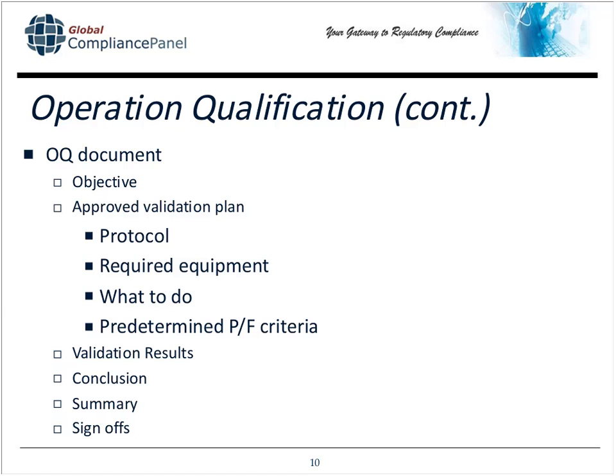Generally speaking, the OQ document is going to have an objective, what you're trying to do, and the approved validation plan. I can't recommend more that you have an approved validation plan, including a protocol, what equipment you're going to use to validate this piece of manufacturing equipment, what you're going to do, and your predetermined pass-fail criteria. As I mentioned earlier, the pass-fail criteria is critical. You've got to know what you need to see before you begin your actual testing. And the protocol itself will be signed off and approved before the conclusion. The results are gathered and the conclusion and summary are signed off.